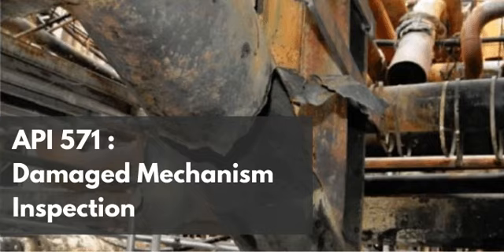That is wild. Yeah, the chemical environment, anhydrous ammonia with a trace of oxygen, will exploit the residual weld stress in an atmospheric tank just as aggressively as it will in a high-pressure sphere. That is a very sobering reality for tank farm operators. You can't just rely on low operating pressure to keep you safe.